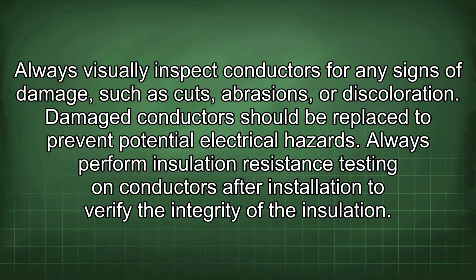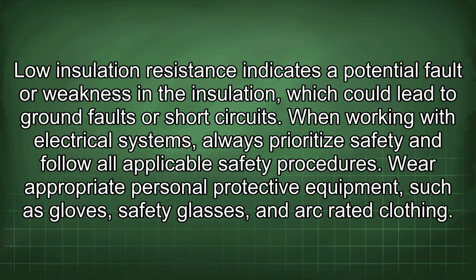Damaged conductors should be replaced to prevent potential electrical hazards. Always perform insulation resistance testing on conductors after installation to verify the integrity of the insulation. Low insulation resistance indicates a potential fault or weakness in the insulation, which could lead to ground faults or short circuits. When working with electrical systems, always prioritize safety and follow all applicable safety procedures.